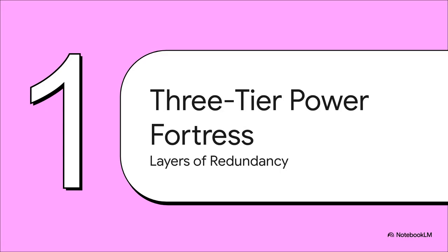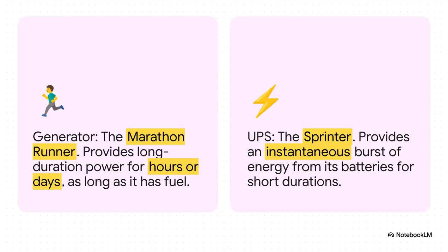Well, you build a fortress. Not with walls and stone, obviously, but with layers and layers of redundant power. It's this incredibly sophisticated, three-tiered defense system, and it's designed to make sure that the servers inside never, ever lose electricity. Okay, to really get how this system works, think of its two main backups as different kinds of athletes. On one hand, you've got the massive diesel generator. That's your marathon runner. It can provide power for hours, even days, just as long as you keep feeding it fuel. Then, on the other hand, you have the UPS, which stands for Uninterruptible Power Supply. Now that's your sprinter. It provides this huge, instantaneous burst of energy right from its batteries. Each one has a very specific and absolutely crucial job to do.